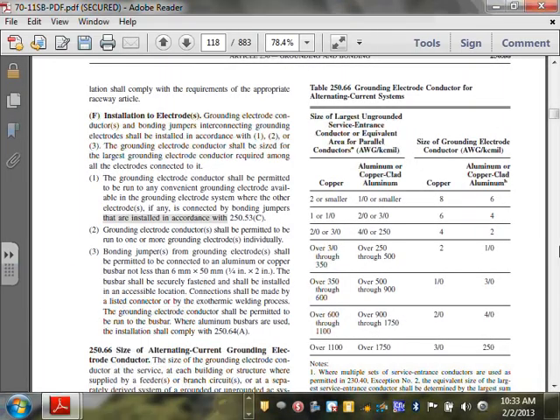Okay, so the notoriously famous 250.66, that's what we were on, guys. The system that we were sizing is over 350 through 600, which will get you 1 aught copper or 3 aught aluminum. I'm sure if you're a journeyman or master, you have seen this enough in your life, right? So I just flashed this one here.